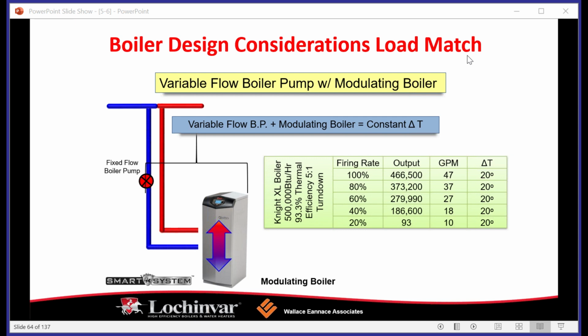Okay, so we're discussing design considerations for load matching. So again, the modulation of the boiler should always be matched to the pump flow, or vice versa. The pump flow should always be matched to the modulation of the boiler in order to make sure we maintain our constant delta, which in turn is going to help to keep us maintaining our efficiency and make sure the boiler is running the way that it should.